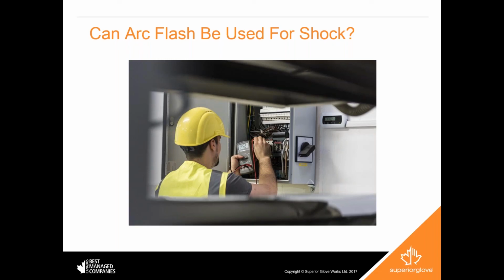And what's going to cause an arc flash to stop? Yeah, absolutely. So on an industrial scale, there's large switches or circuit breakers that are designed and they're in place to flip quickly. So your arc flash won't really be a sustained explosion. It'll be fairly quick, but the area between the two surfaces will quickly separate and the arc dies off because of those switches and circuit breakers. Most energized machinery is made with arcing contacts. They're going to capture the arcs and direct the arc into specially insulated containers so it can't cause any more trouble. And in some cases, your medium or your high voltage circuit breakers, they'll actually have vacuum tubes or special gases which are designed to extinguish or suppress the arcs.